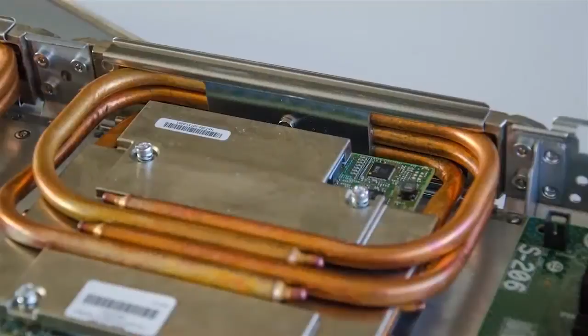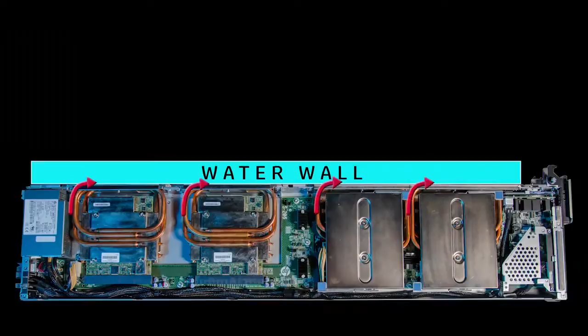Well, that's interesting, because it's basically a water-cooled system with component-level liquid cooling for both the processors and the memory, but with technically no water in the tray. Wow. And the way we do that is by using those heat pipes. They transfer the heat from the processor all the way to that dry disconnect, and that's where the heat gets captured and transferred into the water wall that's in the rack, and that goes to the facility.